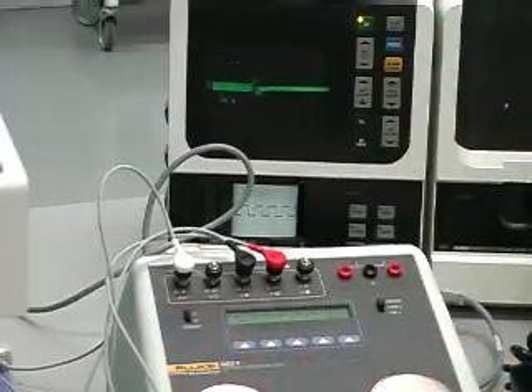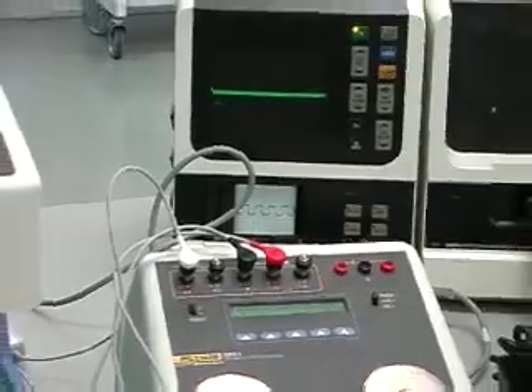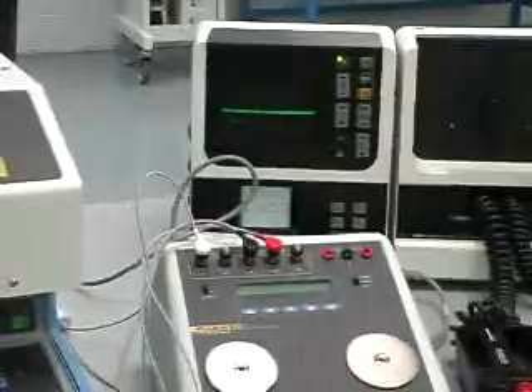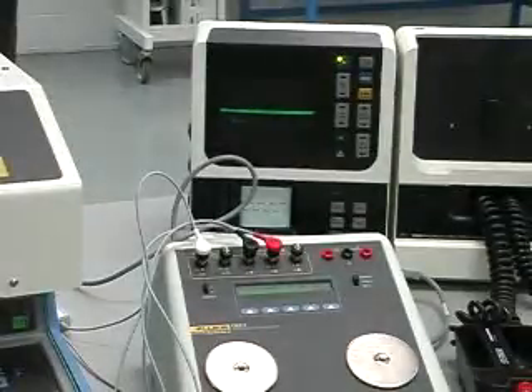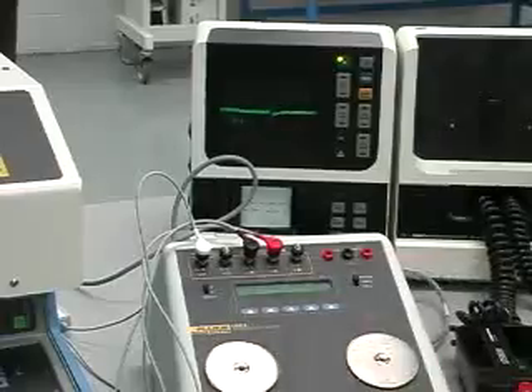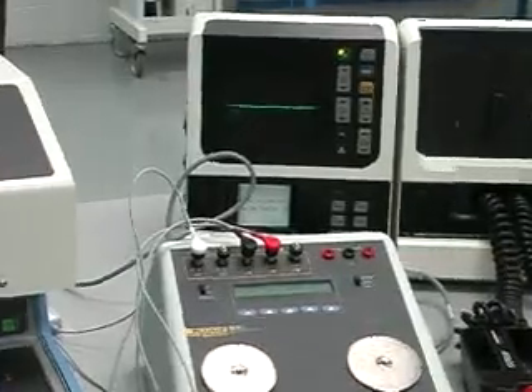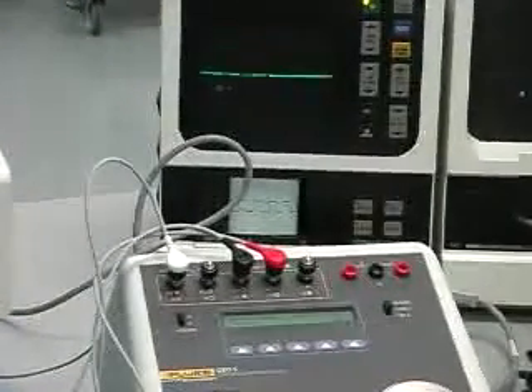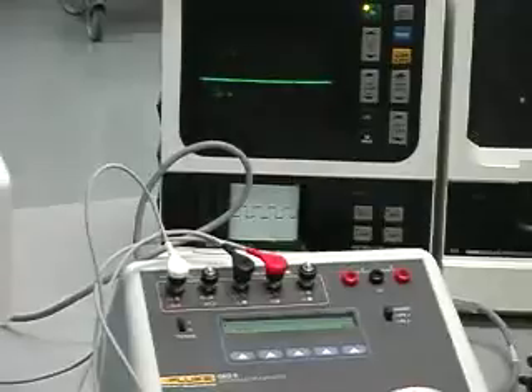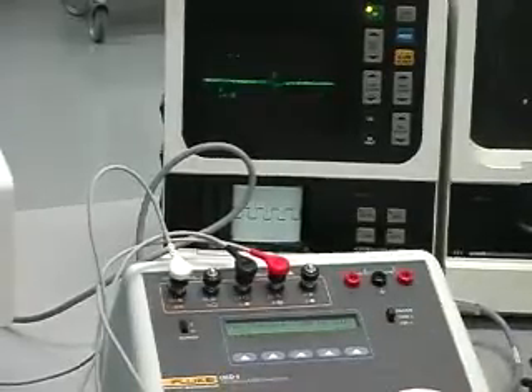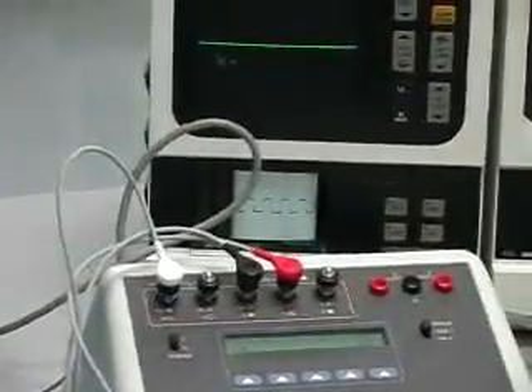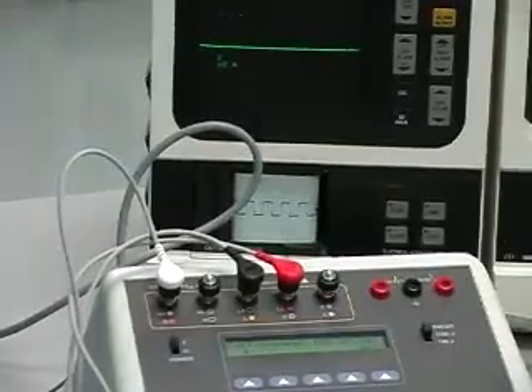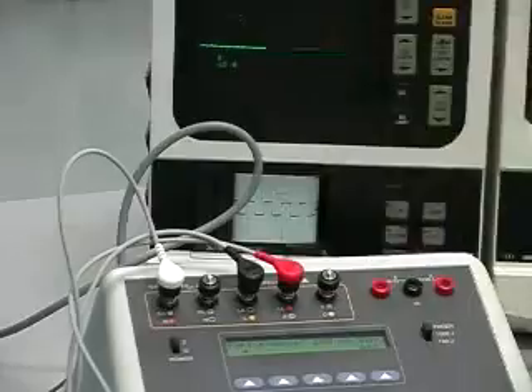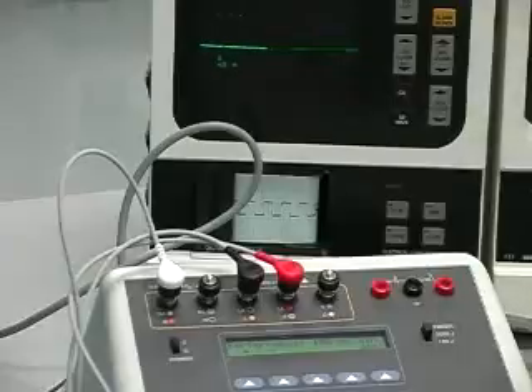50 hertz would be your notch filter test for your international devices that are being powered off of a 50 hertz power system. And 60 hertz. So it is a lot more attenuated at the 60 hertz. So obviously this one's set up for U.S. operation. 100 hertz, that's your 3 dB down point for diagnostic quality, since the monitor shows, and basically the monitoring quality response is already turned way down to practically nothing, just simply to avoid any problems with noise generated by line frequency or by motion.